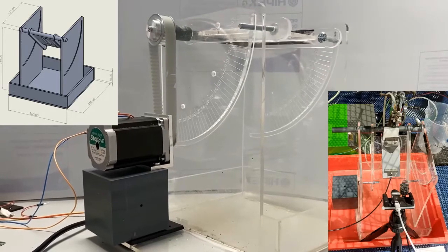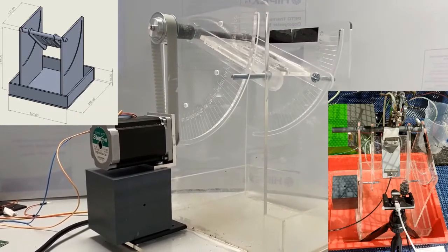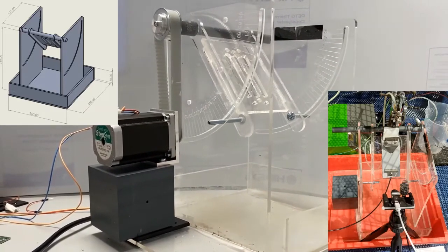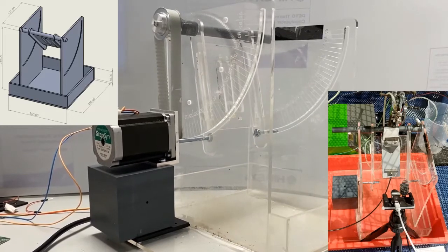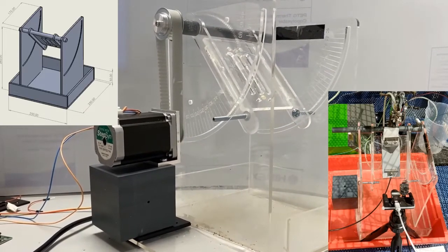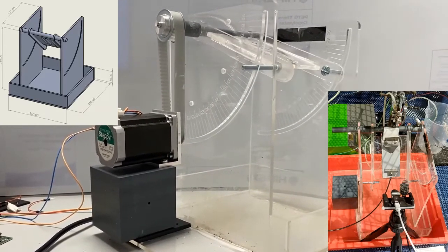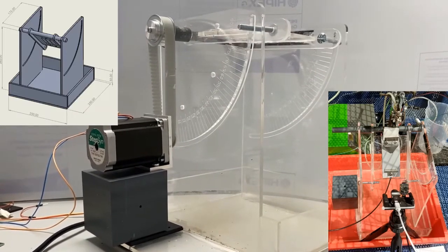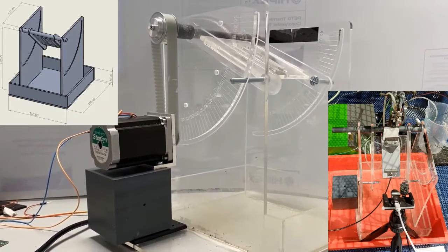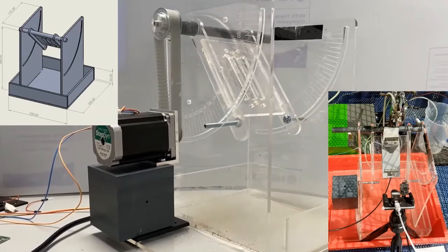So how do engineers test the performance of insulators? What equipment is required? And can coatings become commercially viable? Answering these questions was the aim of the project. The first step was to design and fabricate a tracking rig to hold the samples on the top side. This is to encourage the formation of conductive paths. It incorporates an angular motion mechanism to allow the samples to be set at any inclination between 0 and 90 degrees, 45 degrees being the optimal.